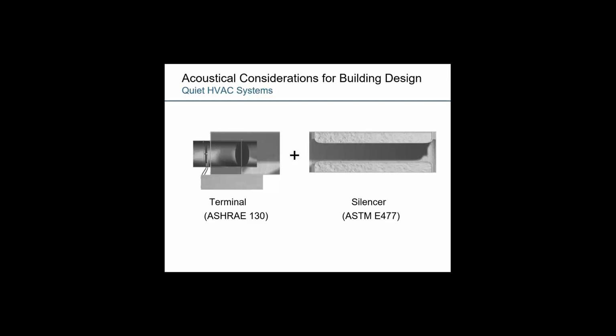And I mentioned and showed in quite good detail the ASTM standard for silencers earlier. What happens is that when a silencer tested in that configuration for ASTM E477 is close coupled to a terminal unit, the overall results can be what we call unpredictable. And I want to take a minute to explain why that is.